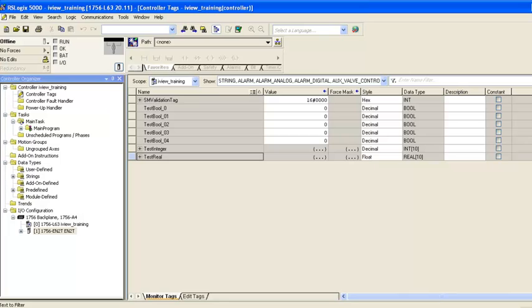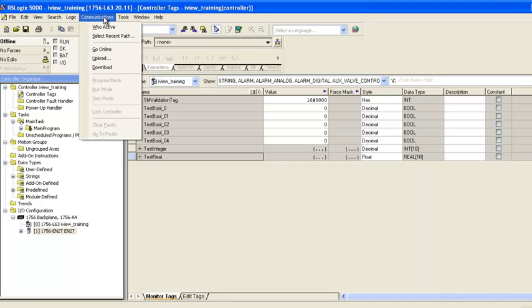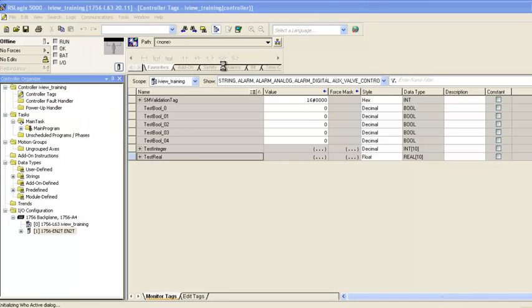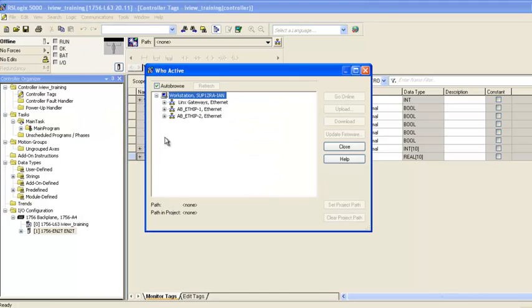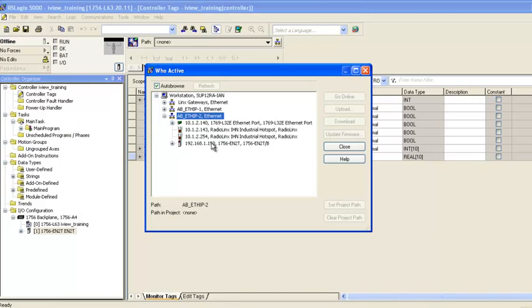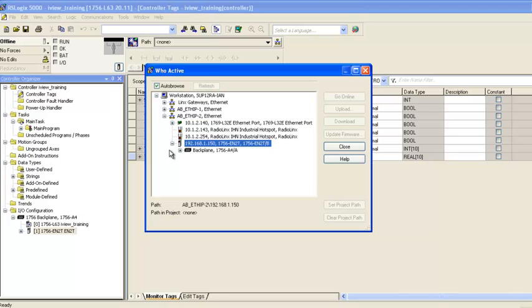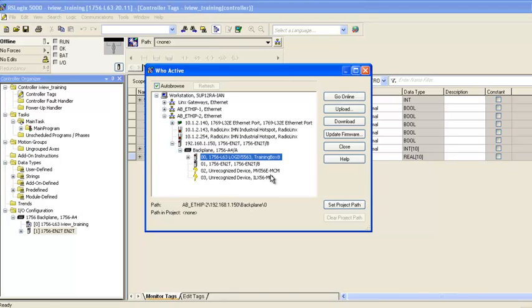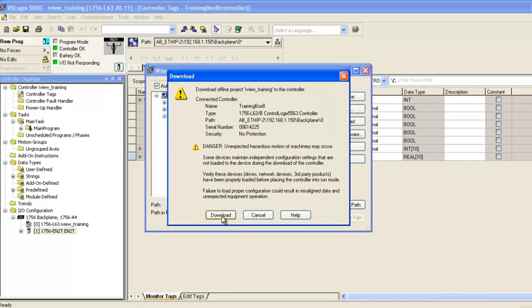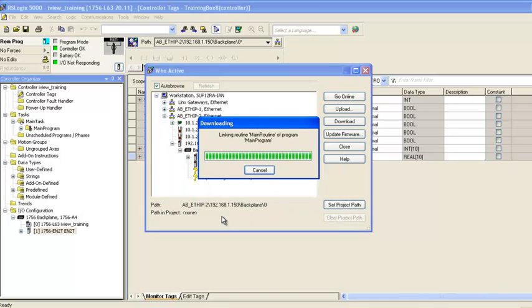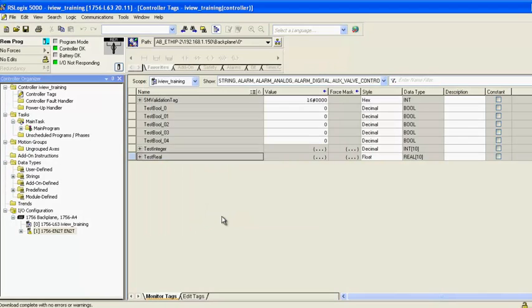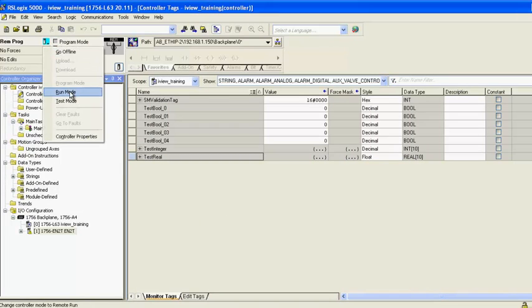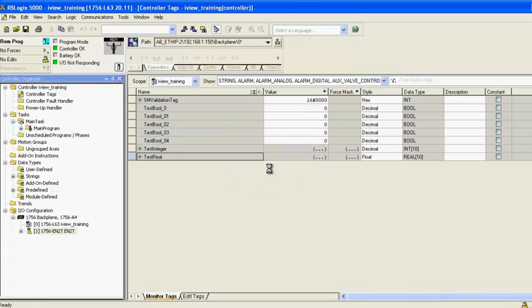Now I'll download the project and go online with RSLogix 5000 to verify wireless communications to the ProSoft iView. To begin, I'll go back into RSLogix 5000 to my project and using the Communications menu, I'll choose Communications and go down to WhoActive. When the WhoActive window opens, I'll expand the AB Ethernet IP driver and select my processor. I'll click Download in the confirmation window and click Download again. Once the project is downloaded, I'll choose Yes to place the processor into Run Mode and go online.